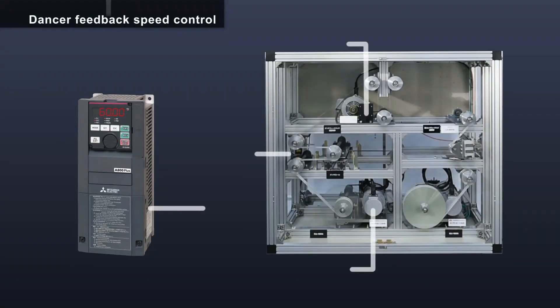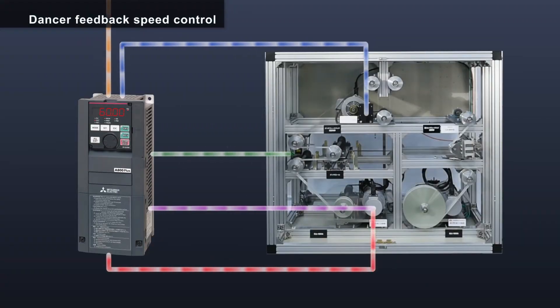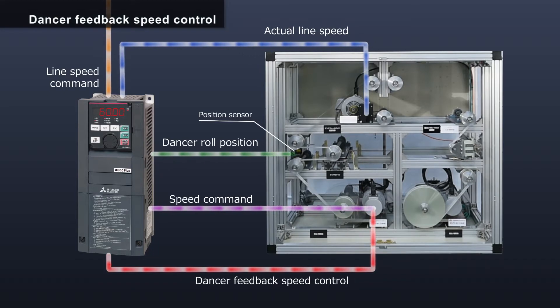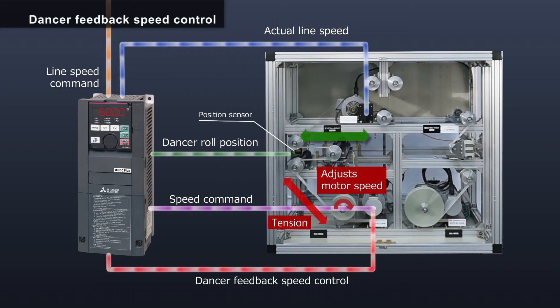The dancer feedback control maintains constant tension on the dancer roll by keeping the roll in place, utilizing line speed and dancer roll positioning data to adjust the speed of both the winding and unwinding shafts.